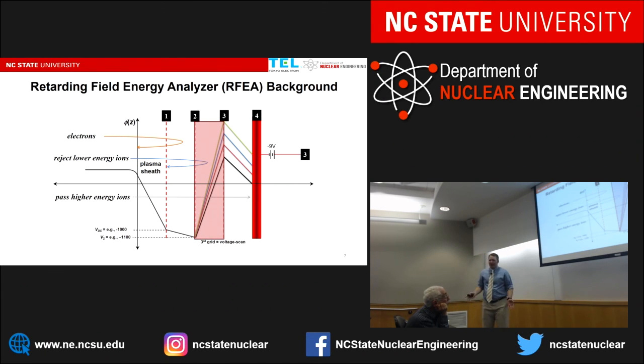So I've talked about RFEAs, but it's good to explain how they actually work. If here on the left you have your plasma, you're going to have electrons and ions that stream from your plasma through your sheath. In the sheath region, there's a potential change, so the ions gain energy, while most of the electrons will get sent back to the plasma. However, some of the very high energy electrons will continue past this first grid. The first grid is set there to basically mimic whatever potential the RFEA is sitting on top of, because you don't want the RFEA to disturb the sheath or the plasma above it. You want it to be the same so that the ion energy that's hitting one part of the electrode is the same as what's hitting the actual sensor. So then you can be consistent in knowing that the ion energy you're measuring is the same everywhere, or uniform, trying to get uniformity.